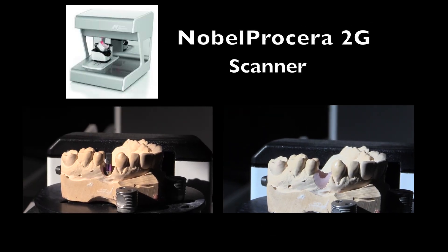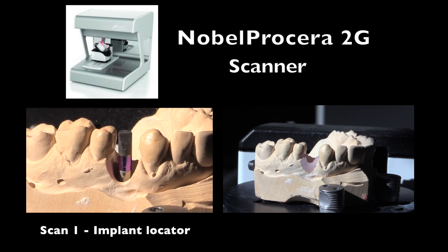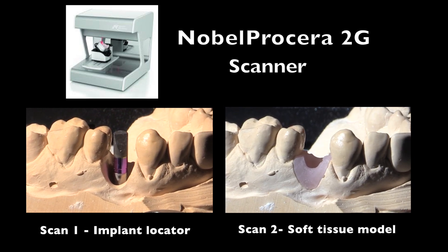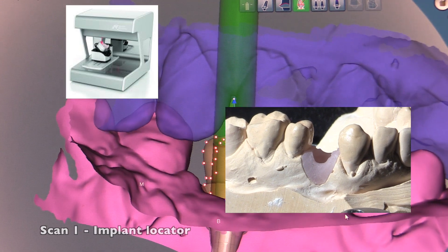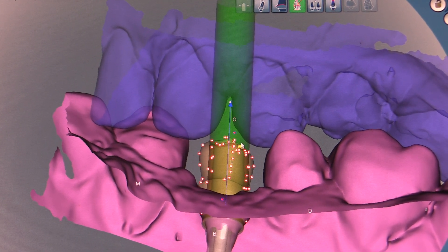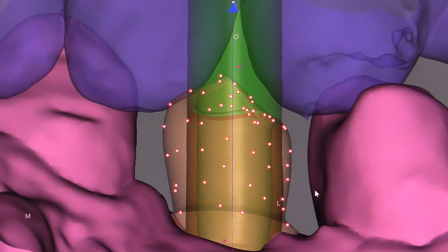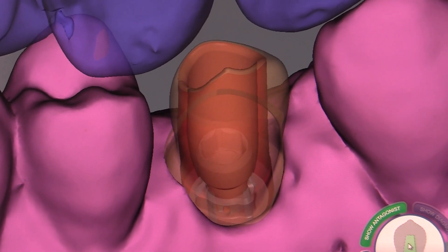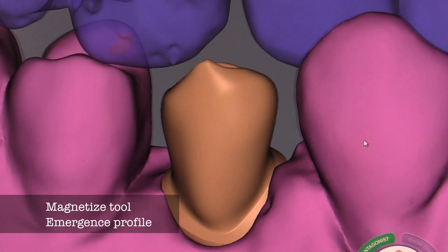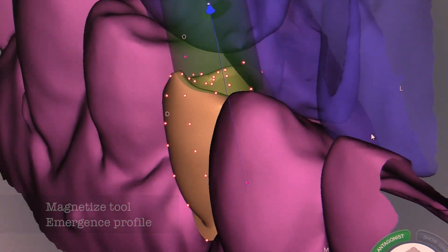We begin by scanning — we do a scan of the implant locator itself, the soft tissues, and also the opposing arch so we can place all of these together on the computer to design our abutment. Once all the models have been scanned, you can align them in a 3D digital model to enable the design of the abutment. You can see the minimum thickness of zirconia, and the emergence profile of the original soft tissue model is captured. The abutment will be magnetized to the side of this to have the perfect shape coming up from the implant to tissue level — this is called the magnetize tool.